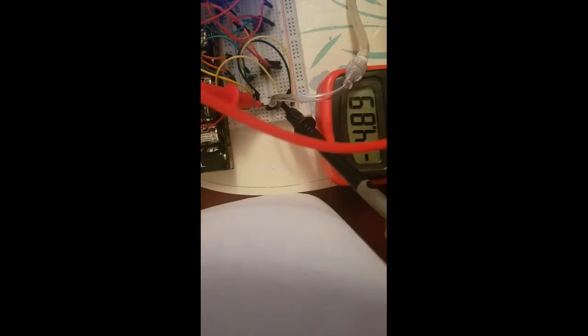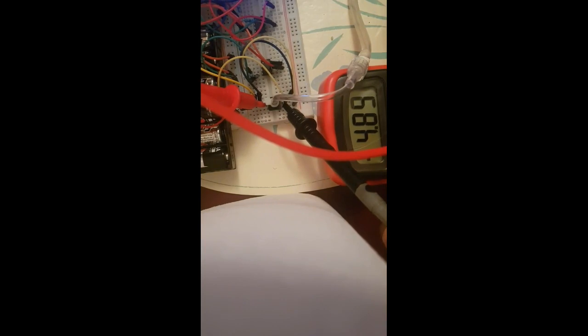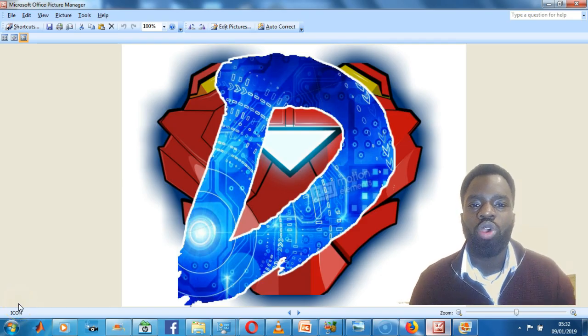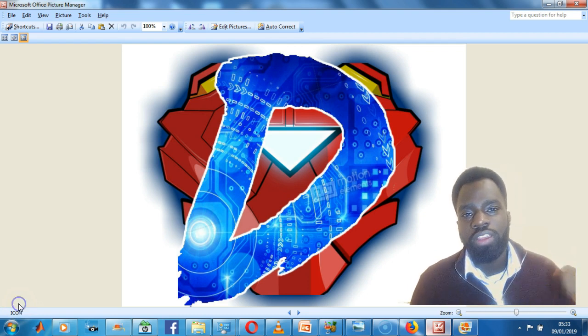We have 4.89 volts supply voltage which isn't quite 5 volts but should be sufficient for the pressure transducer to work properly. Hopefully now you have a better more complete understanding of how a pressure sensor works.